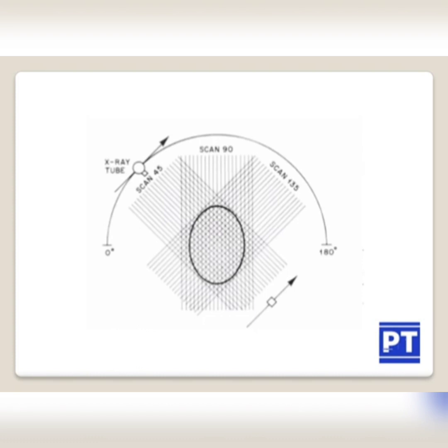The X-ray beam was on throughout the linear movement. When it is moving linearly, the X-ray beam is on, and when it is rotating, the X-ray beam is off during the rotatory movement. The total number of transmission measurements was the product of the number of linear measurements — 160 — and rotatory steps — 180 — which was 28,800 in the original EMI scanner.